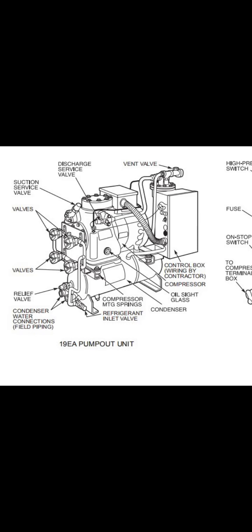A unit may have a pump down unit, centrifugal. Sometimes it doesn't have the pump down unit. In some plants I see each chiller has its own pump down unit with piping and everything. Sometimes I see a plant where each chiller doesn't have the pump down, but the plant must have one storage tank with a pump down unit. Carrier has this full set of pump down storage tank and pump down unit.